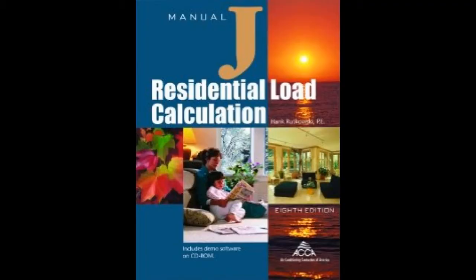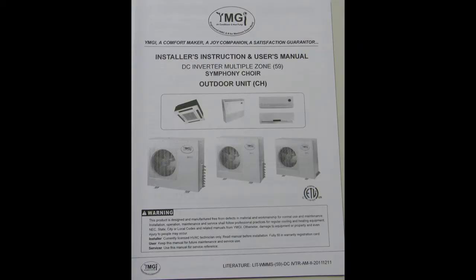Prior to the purchase of the unit, load requirement calculations for heating and cooling should be conducted by the installing technician or contractor for proper unit sizing. Use the Manual J or other reputable HVAC sizing programs to accomplish this task. The installation of a mini-split system is different from that of the standard North American central cooling and heat pump systems. By following the manufacturer's installation instructions closely and using caution throughout the entire installation process, unit failure and damage can be prevented due to steps that can easily be missed during the installation of these units.